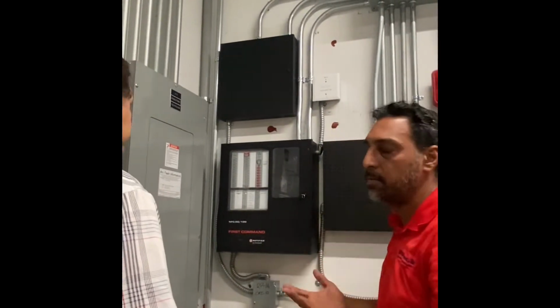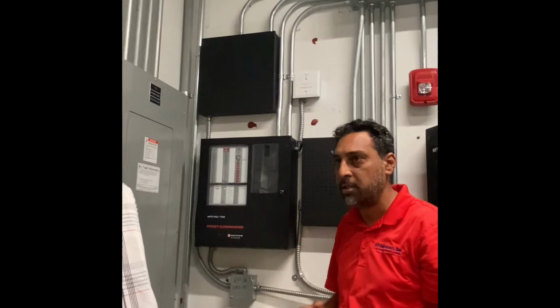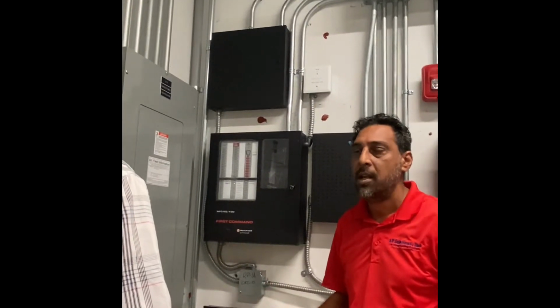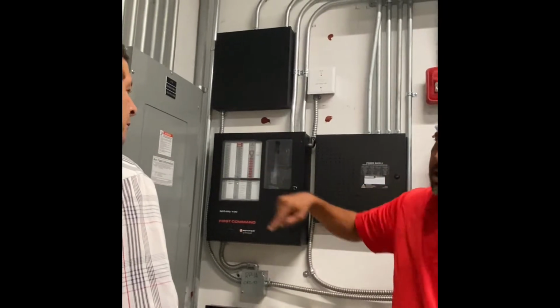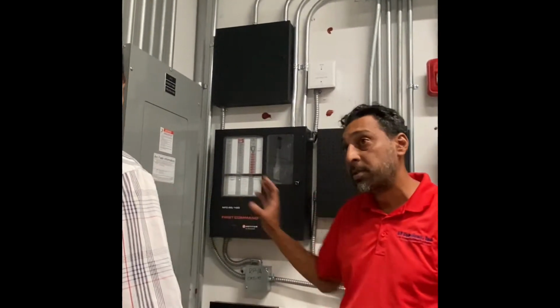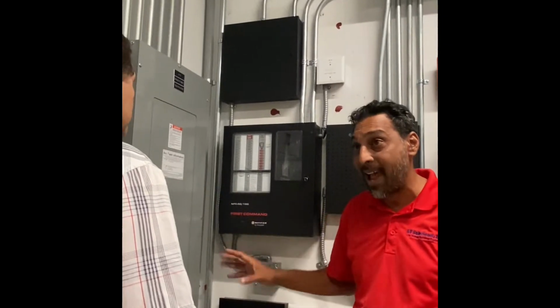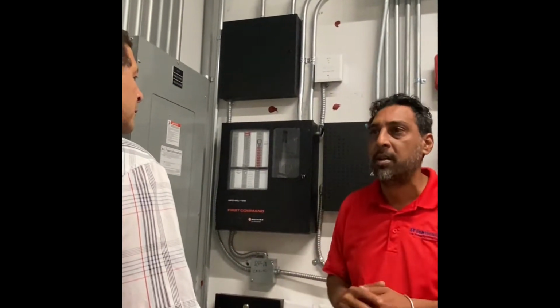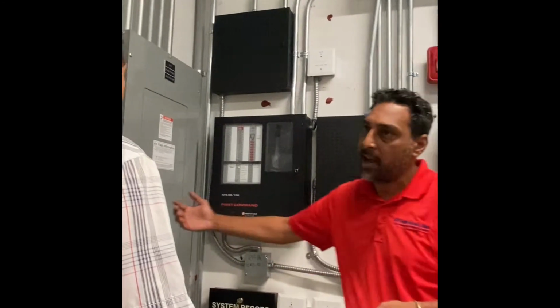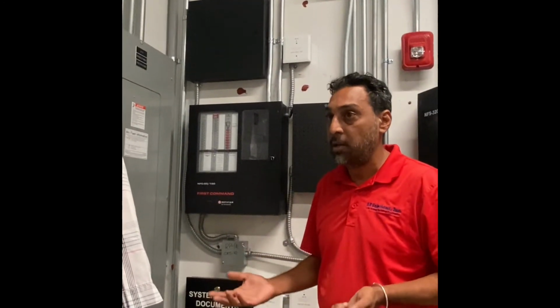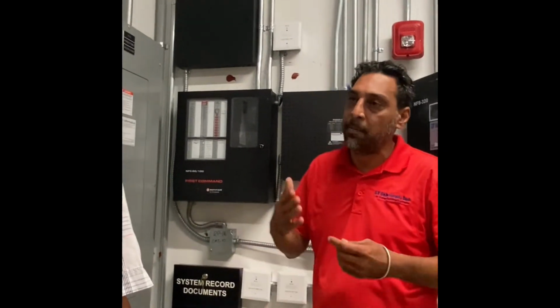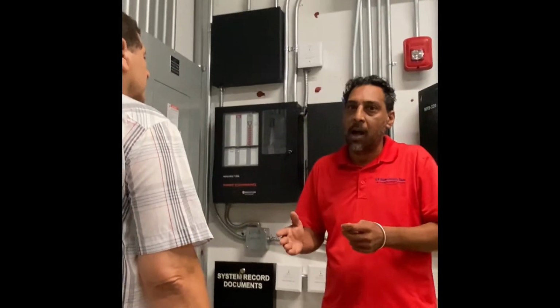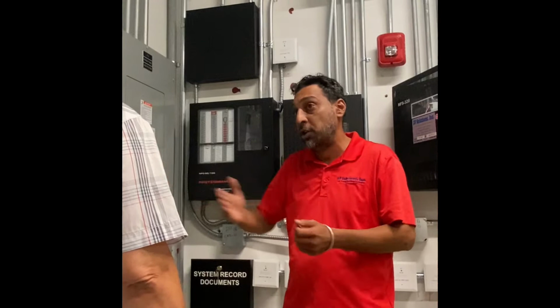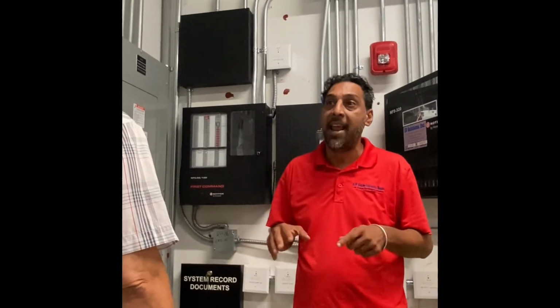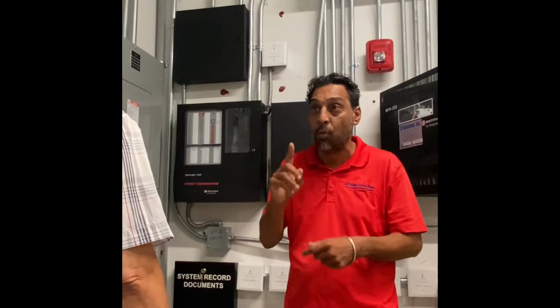Yeah, and your system is what we call Class A out here also. This entire system's Class A. It's for redundancy. What it does, it goes out, hits every device, and comes back home. So if a device in the middle so happens to be pulled out or goes bad, everything around that device still works. The same thing on the addressables. If a device is pulled down in the middle, everything around it will still work, because in Class B you just hit everything and then you have an end. So if anything before that end goes down, then you're losing everything after that. But this system is a Class A system, so there's no losing anything. You're only going to lose one thing if something happens.